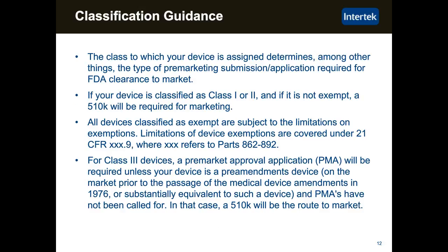So there is guidance on classifying your device. Which class your device is assigned will determine, among other things, the type of submission that you are required to use to gain clearance to market the device. If your device is Class 1 or Class 2 and it is not exempt, a 510K will be required for marketing the device in the U.S. All devices classified as exempt are subject to the limitations on the exemptions, and once again, these can be found for that specific type of device in the Code of Federal Regulations in the different parts.